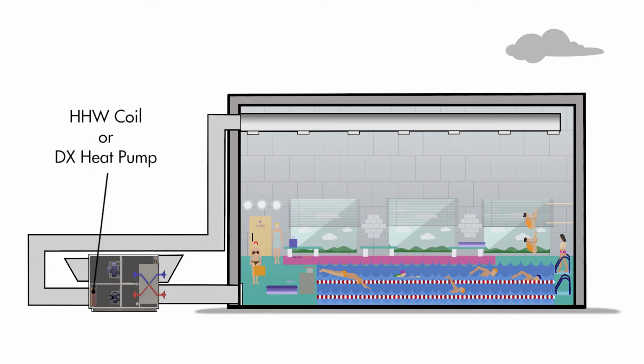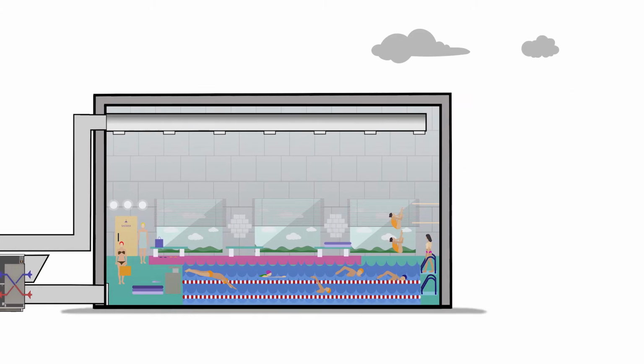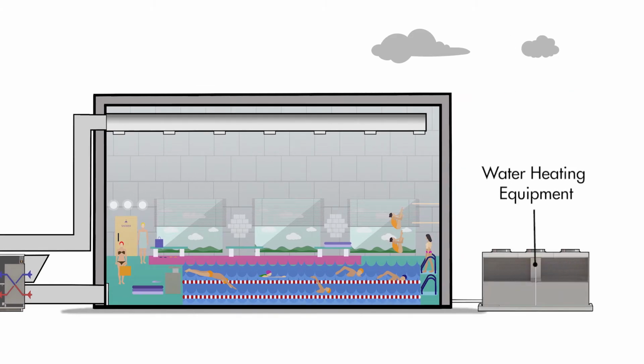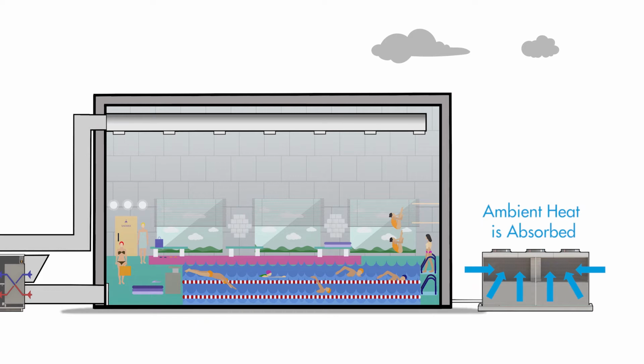The necessary air heating is typically provided by either a hot water coil using a gas boiler system or a DX heat pump. And on top of this, separate equipment is needed for the pool water heating. This is also typically either a gas boiler system or a DX heat pump. Note that DX heat pumps should be the preferable option as they are more energy efficient with a higher COP, or coefficient of performance, which will be discussed later in this video. This is because they use energy to transfer heat from one place to another, instead of transforming chemical energy into heat as is the case with burning gas.